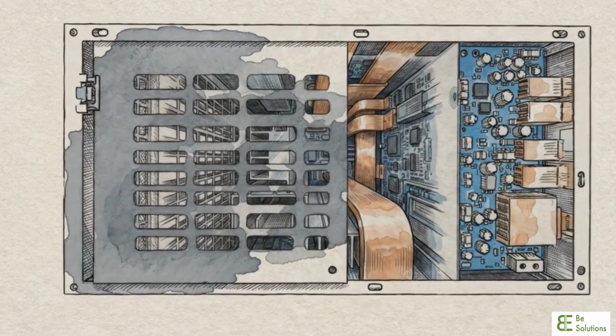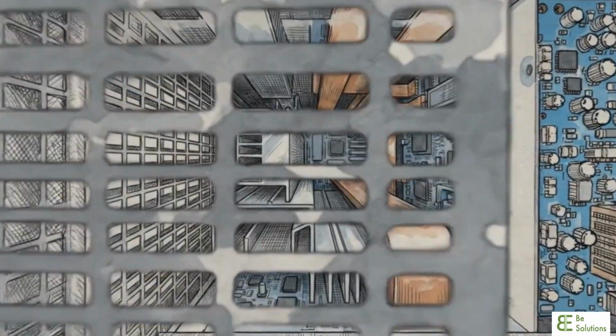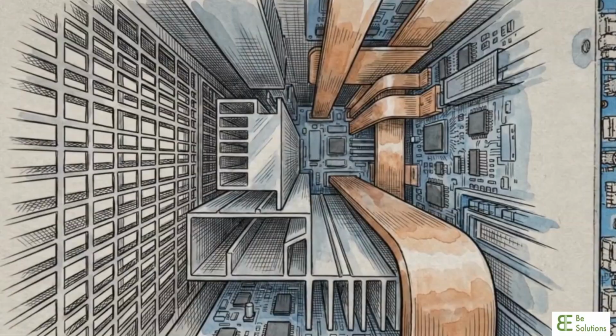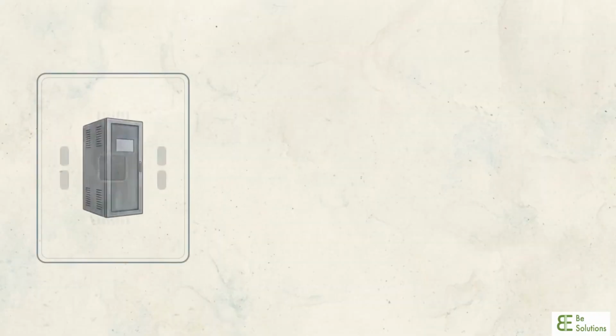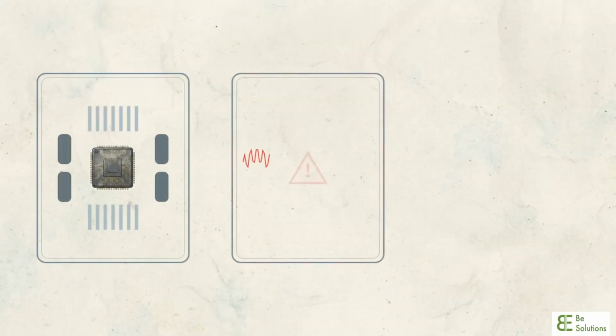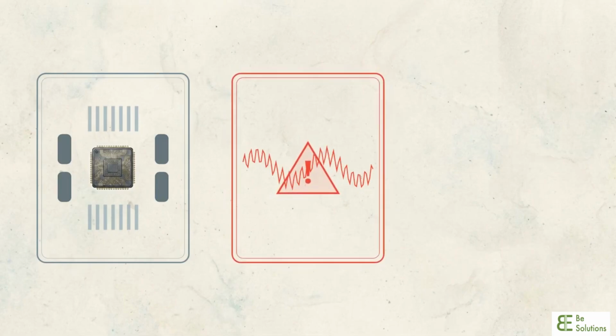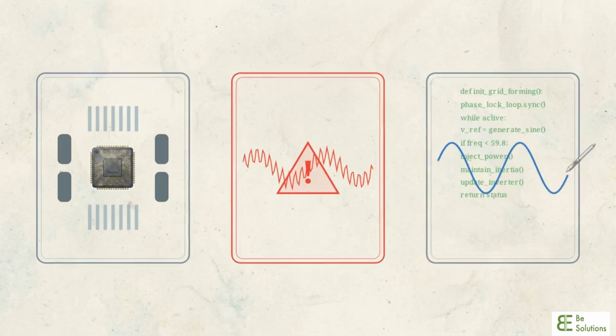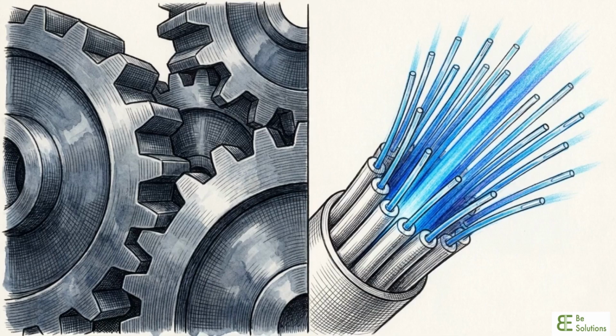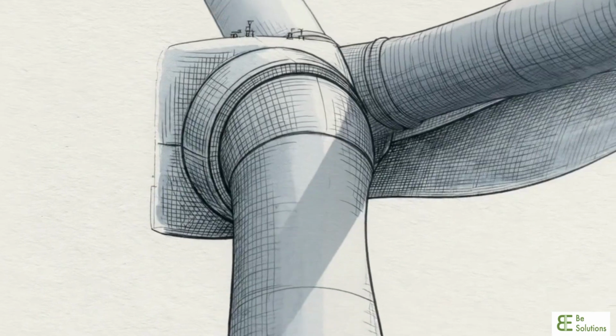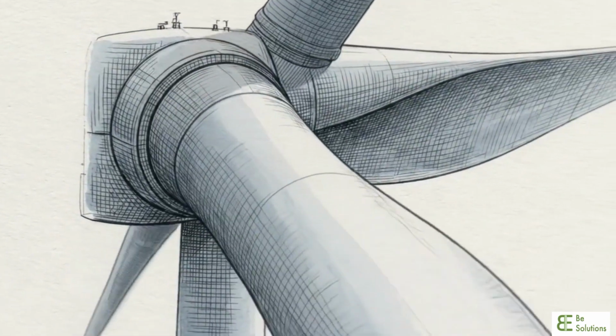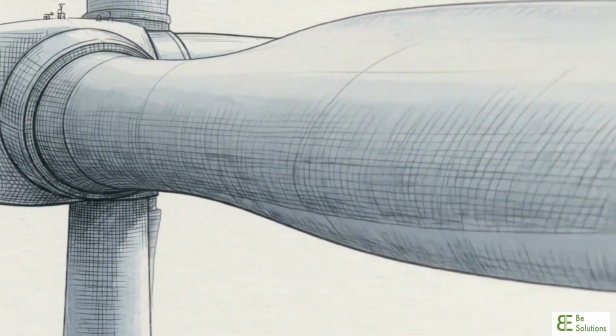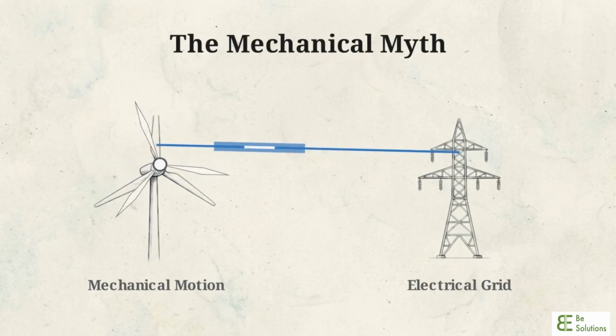To understand how a 100% renewable network actually functions, we have to look inside these systems. We need to deconstruct IBR internal architecture, map the new physics of failure, and analyze the grid-forming firmware required to prevent systemic collapse. The technical hurdle for a zero-carbon power system has evolved from mechanical engineering into a high-frequency data transmission problem. When evaluating renewable assets, there is a persistent assumption that the visible physical components, like the sweeping blades of a wind turbine, directly dictate how the machine interacts with the electrical grid.